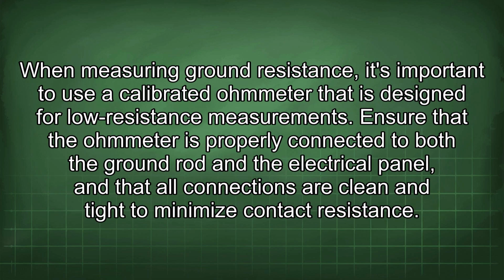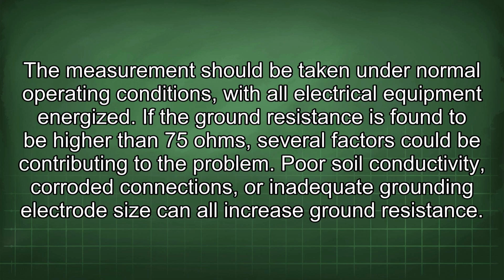When measuring ground resistance, it's important to use a calibrated ohmmeter that is designed for low resistance measurements. Ensure that the ohmmeter is properly connected to both the ground rod and the electrical panel, and that all connections are clean and tight to minimize contact resistance. The measurement should be taken under normal operating conditions with all electrical equipment energized.